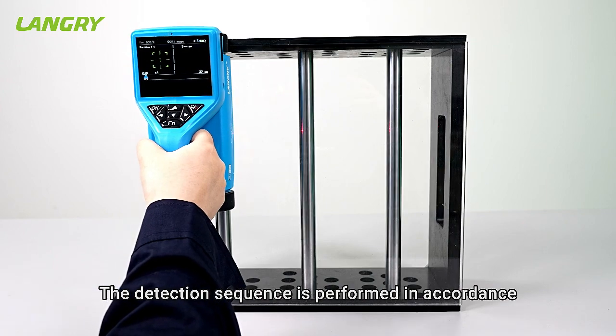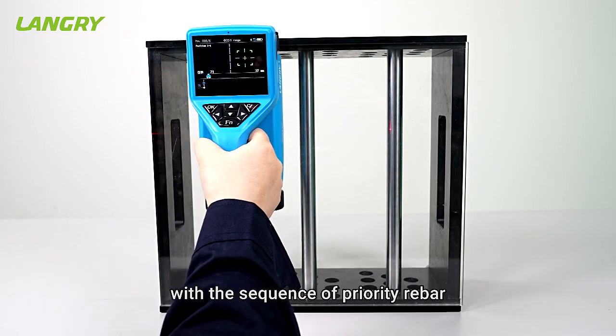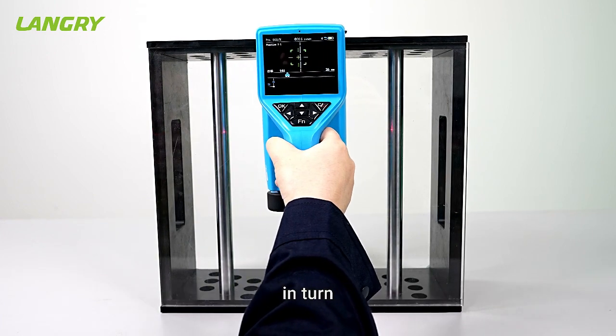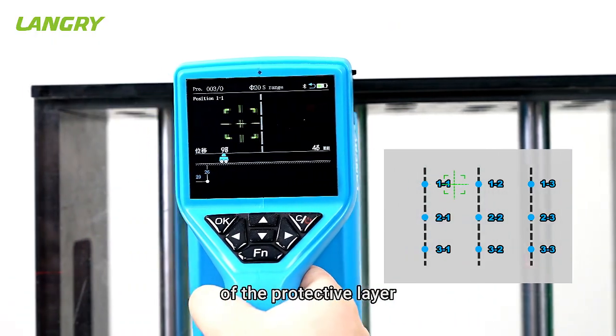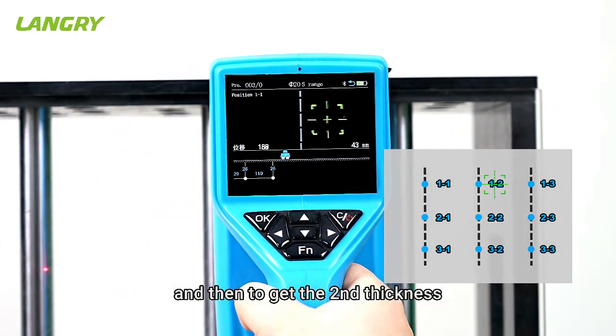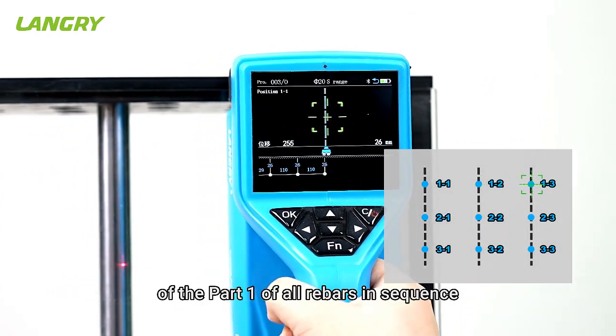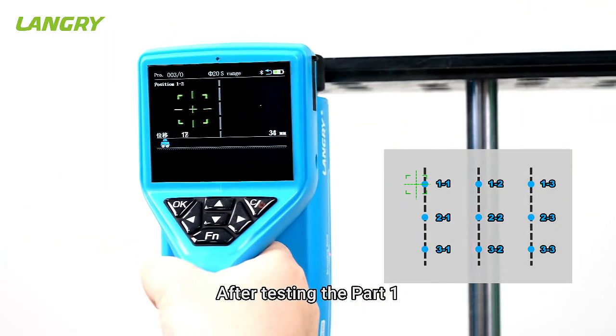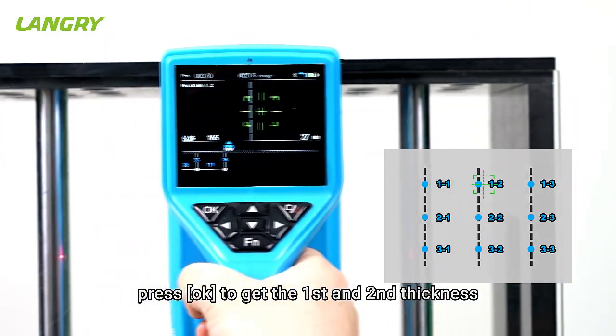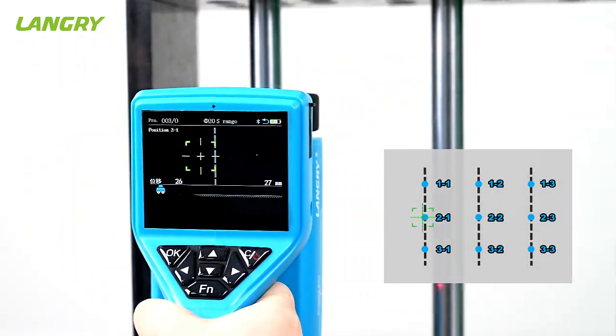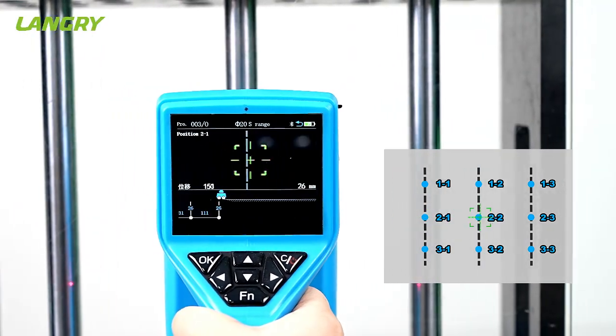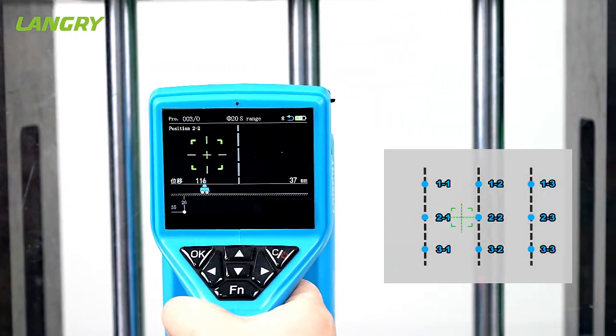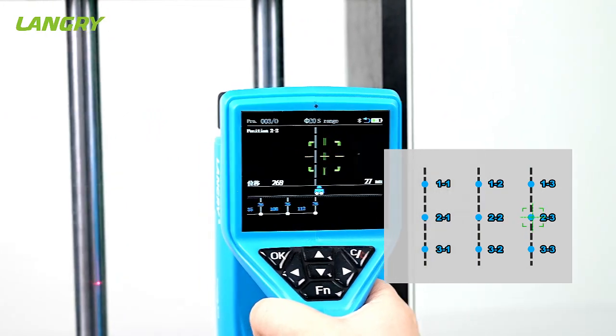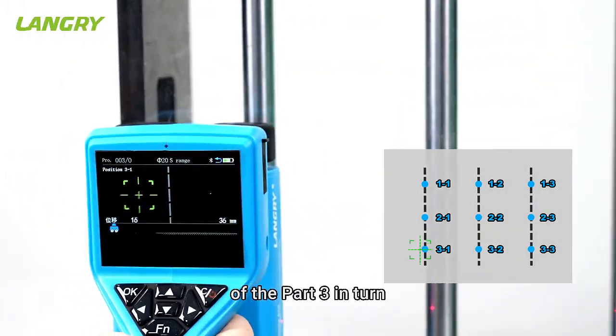The detection sequence is performed in accordance with the sequence of priority rebar, and then in accordance with the detection parts in turn. That is, to get the first thickness of the protective layer of part 1 of all rebars, and then to get the second thickness of the protective layer of part 1 of all rebars in sequence. After testing part 1, press OK to get the first and second thickness of the protective layer of part 2 in the same way. And the first and second one of part 3 in turn.